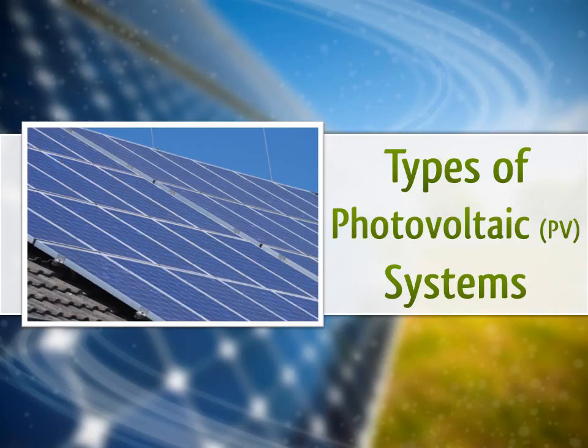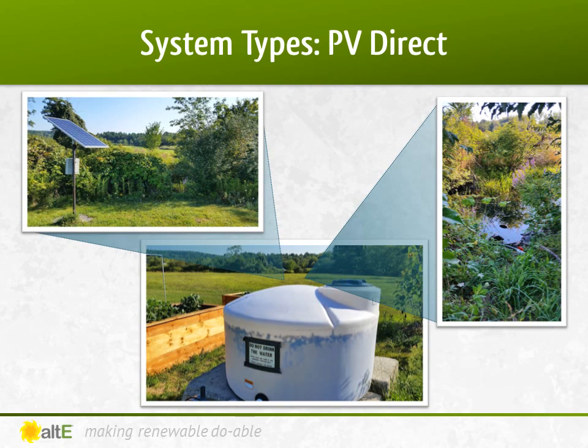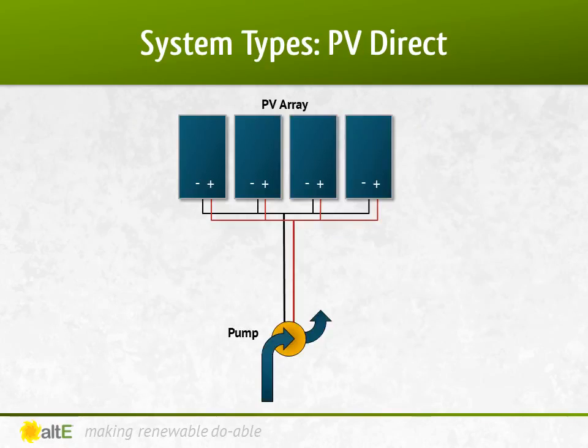Let's start with the different types of photovoltaic or PV systems. PV direct systems are the most basic type. The most common one is solar water pumping for remote irrigation, watering livestock, or pumping from a well or stream to a cistern. A PV direct system can consist of as few as two components: the solar panel and the device being powered, like a pump or fan. There is often a controller or a linear current booster between the two and some fuses and breakers, but not much more than that.